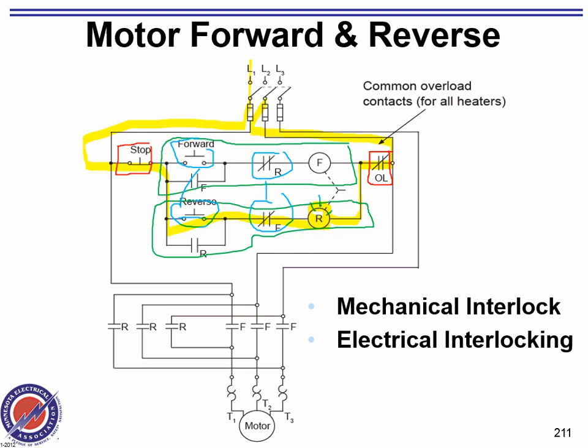Now, once this is energized, then this will close, and the power will diverge into this side. Now, what happened down here? Down here, gentlemen, we're going reverse. These guys will close. 1, 2, 3. And now I am taking phase. Look at phase L1 is switching with L3, and L3 is switching with L1. And L2 stays the same. That's it. Any comments, guys, questions about forwarding and reversing a three-phase motor?